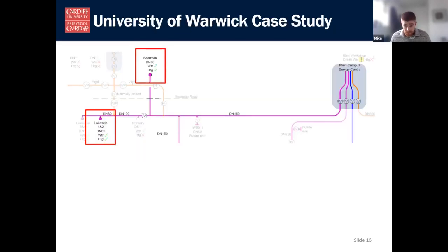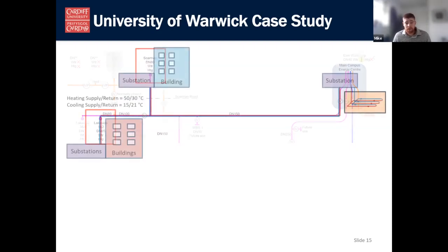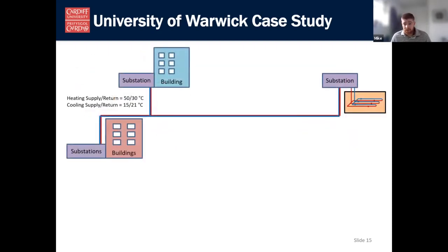And returning to the University of Warwick case study then, this is a diagram of part of their existing high temperature network. We've retained the topology from this network, which connects the main energy centre to 3 buildings, which are Scarman House and Lakeside 1 and 2. And we've replaced this network with balanced heating and cooling network with ground array, for which we assume the building heating loop supply and return temperatures of 50 and 30 degrees C, and for cooling 15 and 21 degrees C.